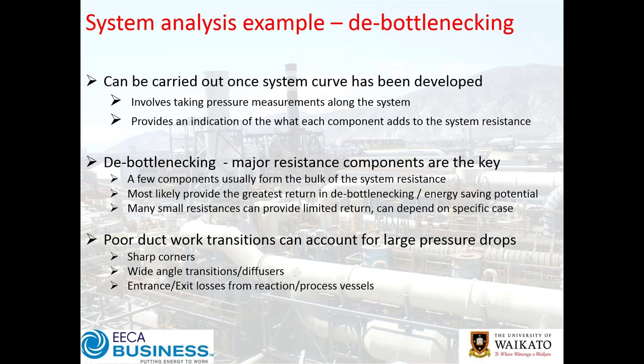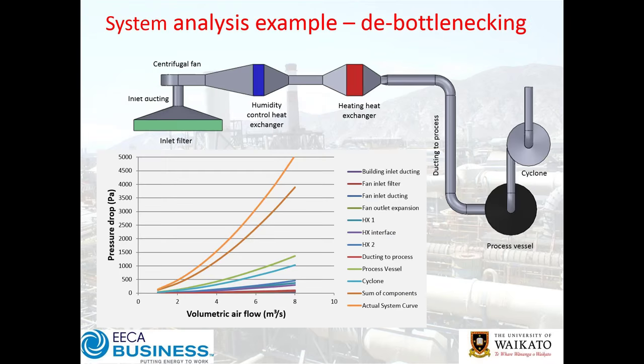Many small resistances can add up but may have too high a price to chase individually — look for the big wins that pay for themselves. As a good rule of thumb, the first place to look is all your duct transitions and inlet and exit conditions as flows come in and out of vessels and other critical components — sharp corners, wide-angle transitions and diffusers, and entrance and exit losses.